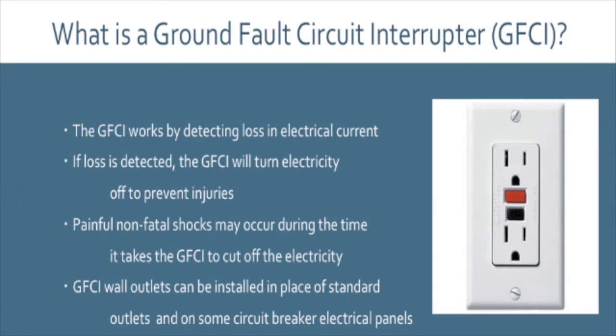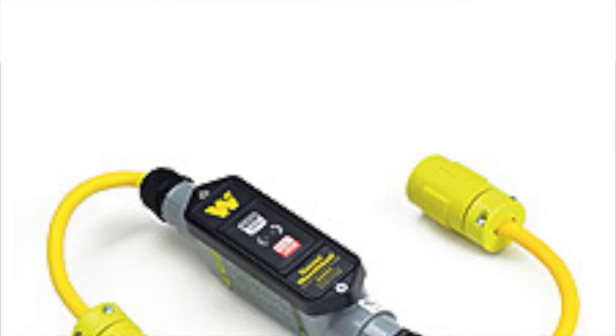NEC 210.8(B)(3) requires that all 15 amp and 20 amp 125 volt receptacles in a commercial kitchen be GFCI protected. When a loss is detected, the GFCI turns the electricity off before severe injuries or electrocution can occur. Painful, non-fatal shock may occur during the time that it takes for the GFCI to cut off the electricity. So it's important to use the GFCI as an extra protective measure rather than a replacement for safe work practices.